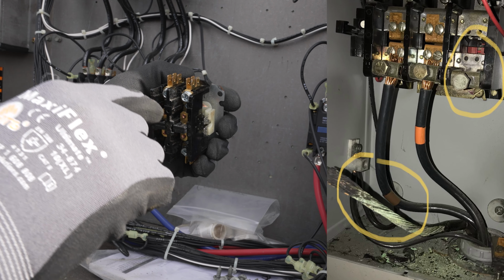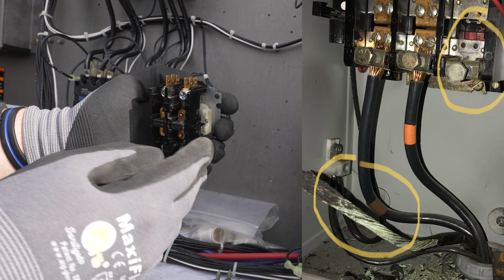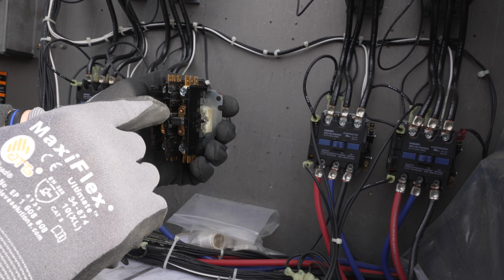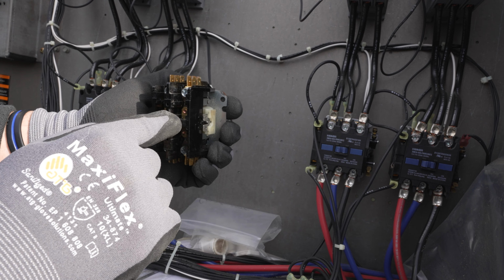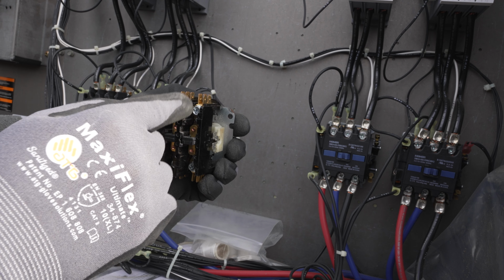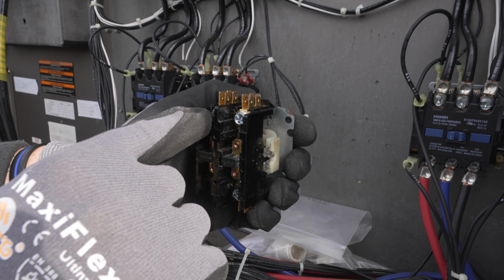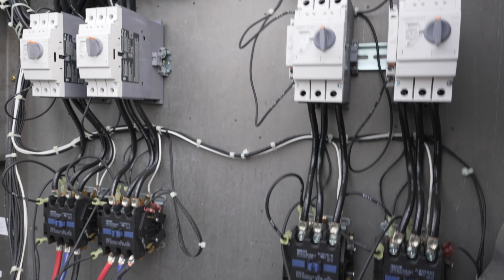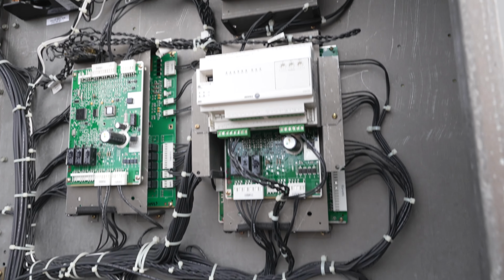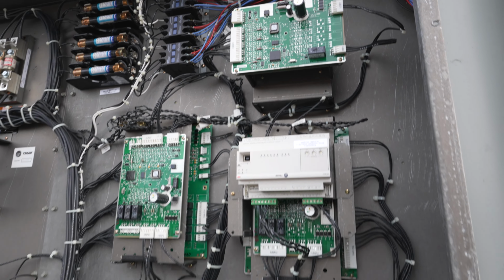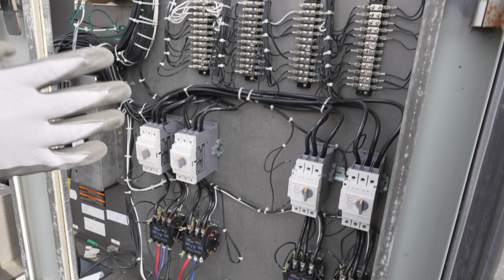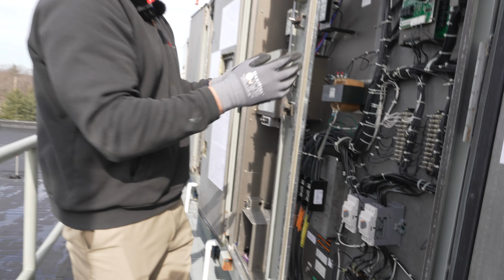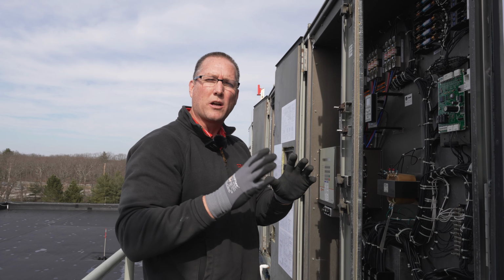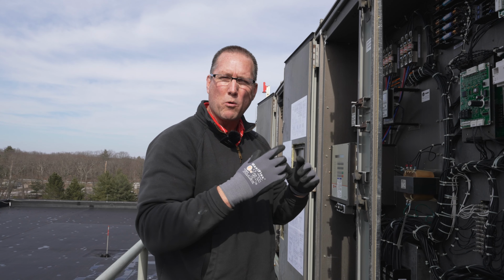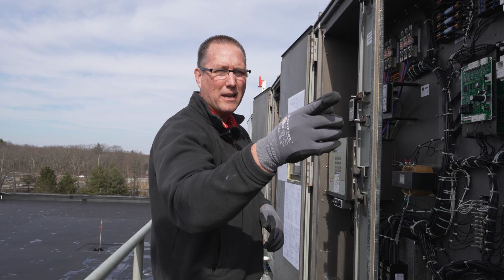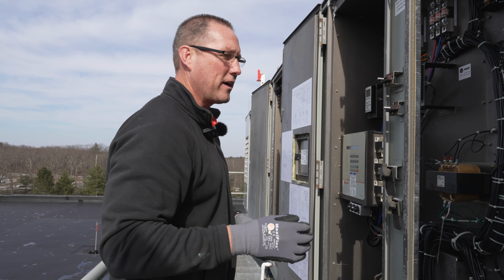We're looking for pitted contacts, because the last thing you want is, as these contacts get pitted, every time that pulls in, we're going to get an arc flash. And it could jump right over there and short out a compressor. Keeping the compressors well maintained, that's the heart of your system, that's the big cost. So all the other stuff, the electrical, we're going to move on to the next section with the filters. Those are the low cost items that we want to make sure we maintain to protect against the major failures.